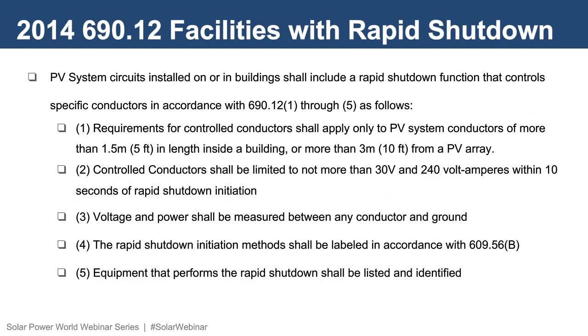The intention of introducing rapid shutdown in the 2014 code cycle was to provide a safer environment for emergency response personnel. Rapid shutdown only applies to PV systems on or in buildings. The code calls for controlled conductors to meet certain requirements based on their location in relation to the physical PV array or arrays. Controlled conductors are those that are 10 feet away from the PV array on the outside of a building or 5 feet within a building.